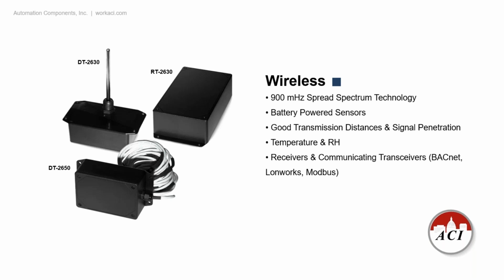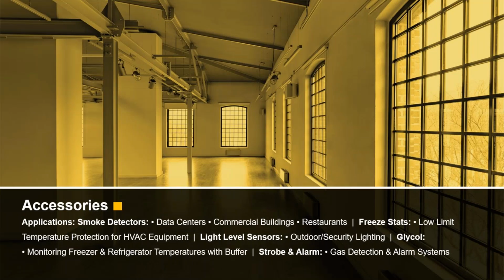We would be able to take your blueprints, again, walk over any plans that you have, show you where we would feel the best places would be for the sensors and repeaters and end modules. This end module converts that wireless signal to an analog output, a LON output, a BACnet output, or a Modbus, whatever you would choose. Some different accessories we get involved with for different applications out there listed.